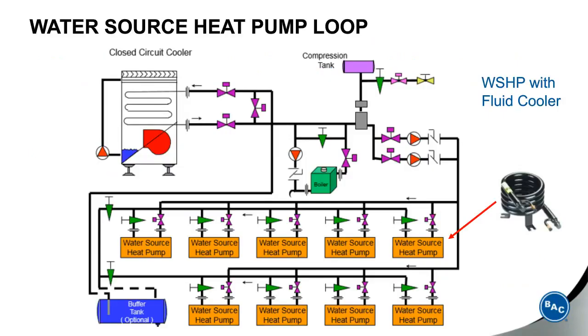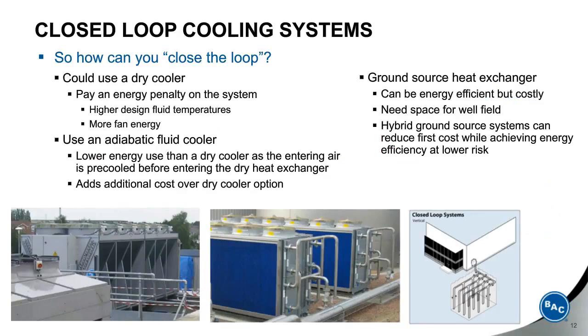Here is a sample diagram of a water source heat pump loop. You can see this one is based on a closed circuit cooling tower with a boiler, and all the orange boxes there are your water source heat pumps located throughout the building, but each one of those has either a brazed plate or a coaxial heat exchanger in them that can be fouled or clogged if this was an open loop. So that's why closed loops are used in these instances. So how can you close the loop?